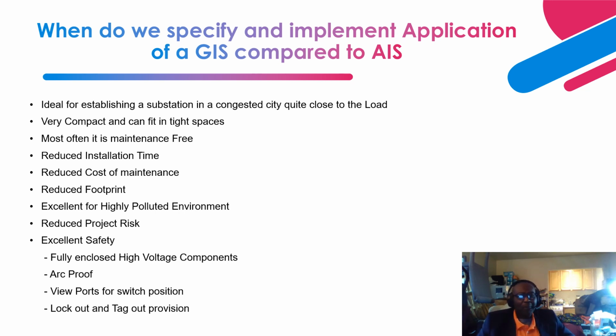Okay. So now let's talk about when we specify and implement the GIS. That is very important as a discipline engineer, where you have to make a decision when to use an AIS substation or a GIS substation. One of the first reasons is if you have a congested, highly populated density city, a city that's choked with buildings, with no space in it. In such a situation, building an AIS substation, an air insulated substation, is not the best choice, because space is at a premium.